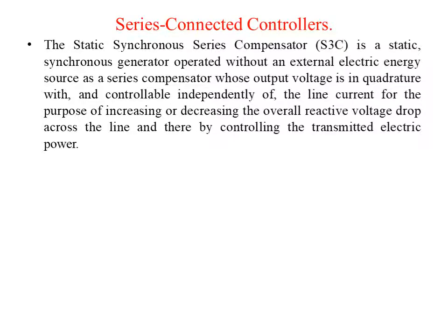The static synchronous series compensator, or SSSC, is a static synchronous generator operated without an external electric energy source as a series compensator, whose output voltage is in quadrature with and controllable independently of line current for the purpose of increasing or decreasing the overall reactive voltage drop across the line and thereby controlling the transmitted electric power.